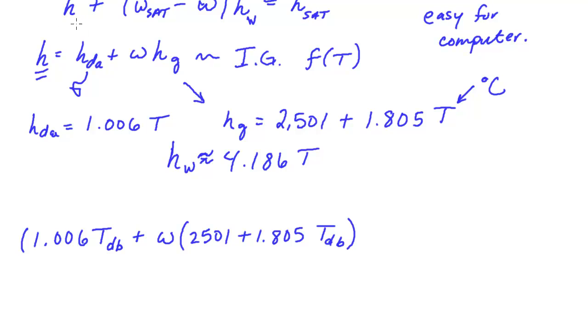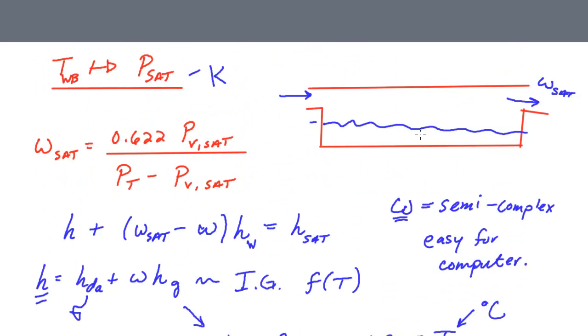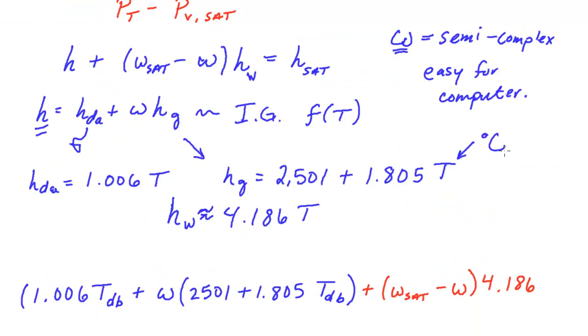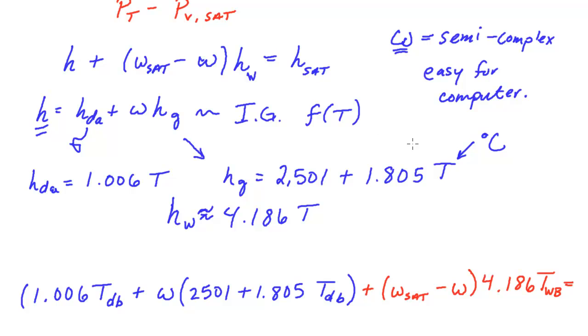We also need the omega at that condition along with this term here, so we have 2,501 plus 1.805 times T dry bulb. That was this first term. We have this next term which was omega sat minus omega times h of the liquid water which we have is 4.186. Remember we've made this definition that at the wet bulb temperature the liquid water that's entering is at that wet bulb temperature.